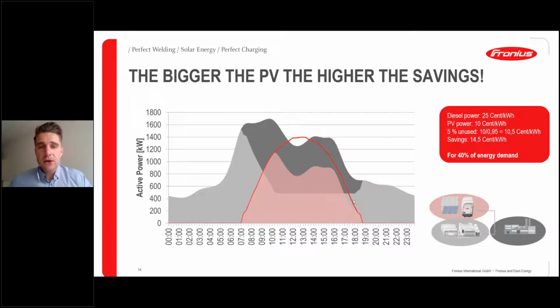That's the case here again. You see now the red line is much higher. The PV system behind this system is much bigger. And therefore, we strongly recommend such a high penetration PV genset system. Such a curtailment, that means an oversizing of the PV system, makes total sense economically, because the genset minimum load has to be obeyed, of course. And you can see here with regards to this calculation that you meet a higher percentage of the energy demand of the load, up to 40%, and have therefore, of course, higher savings. And of course, you have a faster return on investment with such a system.